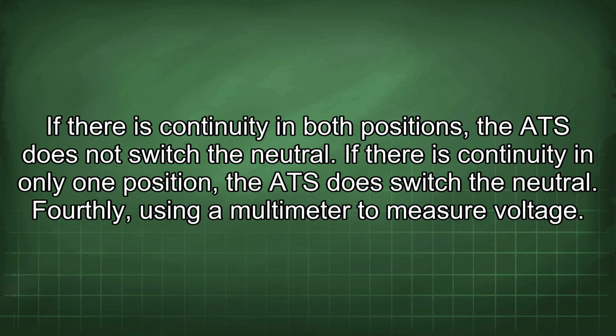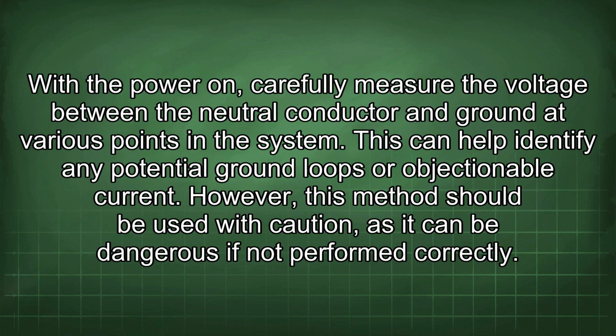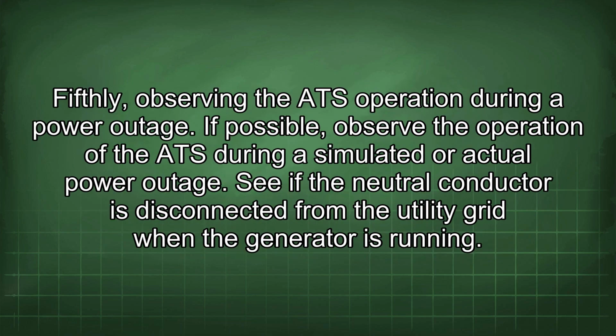Fourthly, using a multimeter to measure voltage. With the power on, carefully measure the voltage between the neutral conductor and ground at various points in the system. This can help identify any potential ground loops or objectionable current. However, this method should be used with caution, as it can be dangerous if not performed correctly. Fifthly, observing the ATS operation during a power outage. If possible, observe the operation of the ATS during a simulated or actual power outage. See if the neutral conductor is disconnected from the utility grid when the generator is running.